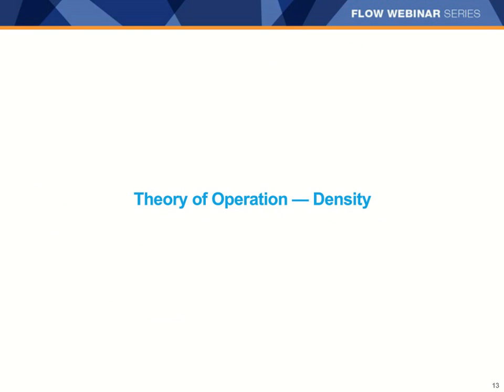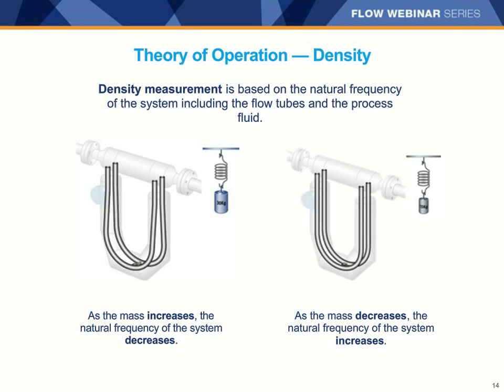Let's now look at how we measure density. Density measurement is based on the natural frequency of the system, including the flow tubes and the process fluid. As the mass increases, the natural frequency of the system decreases. As the mass decreases, the natural frequency of the system increases.